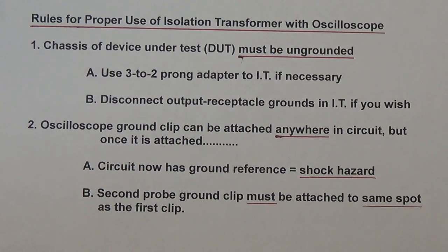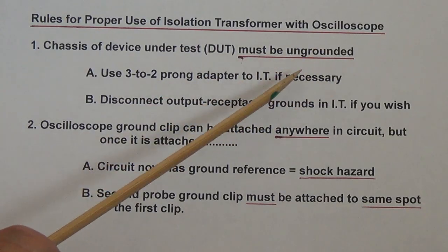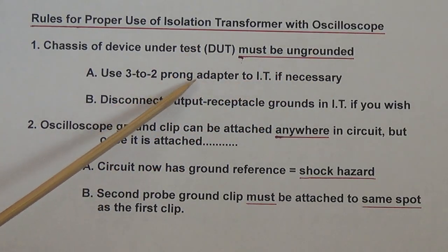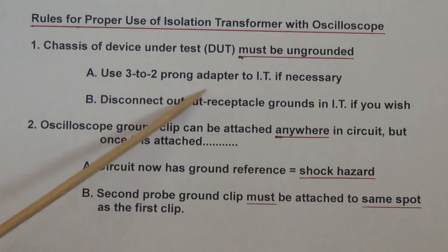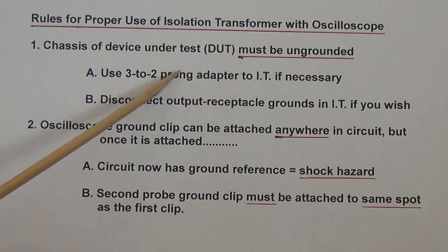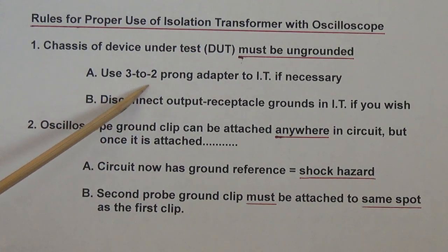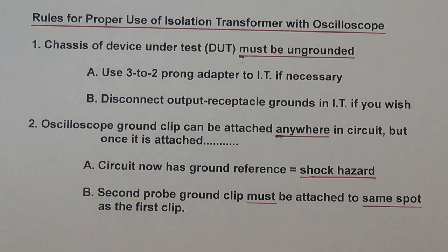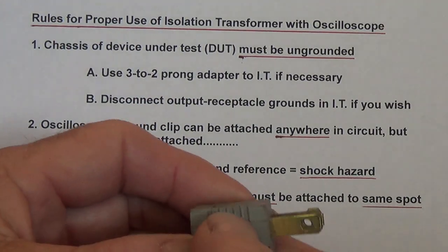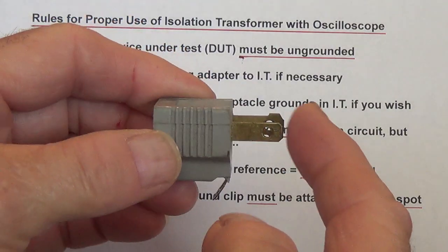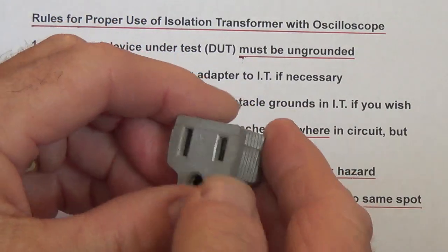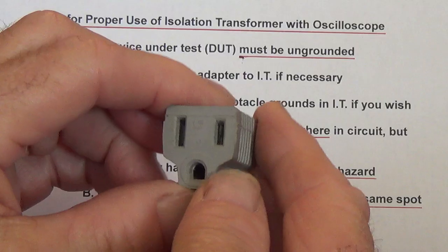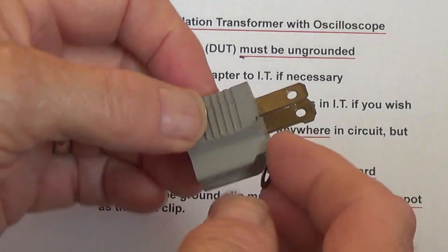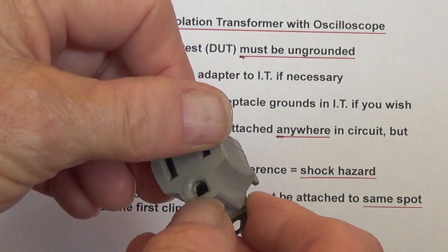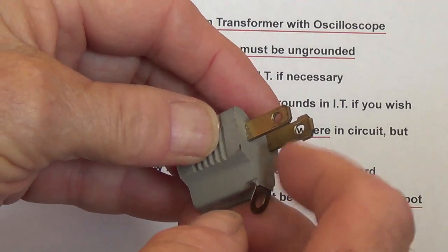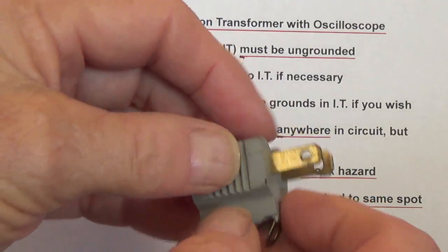Now, if you have a 3-prong plug on the device that you're going to test, you have to either use a 3 to 2 prong adapter that has the polarized 2 prongs on one side, 3 receptacle holes on the other, and no connection between the ground lug and the receptacle in the isolation transformer.